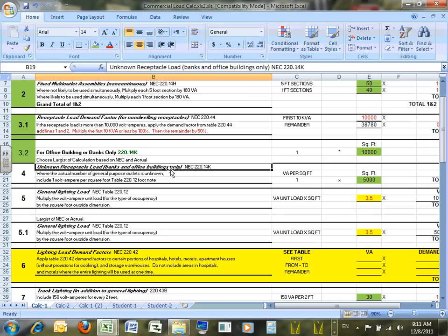Okay, now, the second thing that you need to do for the building that we have, Ashley, is that they want us to size for a future expansion of 5,000 square feet. Right? That's future expansion. If I ask you how many receptacles am I going to have in the future expansion? I don't know yet. We don't have any criteria, any narrative for it. This is where, Chris, you use the 1 volt-amp for future expansion only.